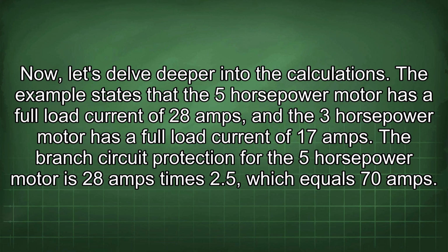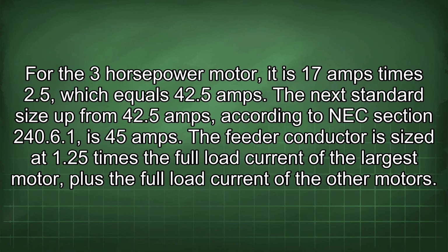The example states that the 5 horsepower motor has a full load current of 28 amps, and the 3 horsepower motor has a full load current of 17 amps. The branch circuit protection for the 5 horsepower motor is 28 amps times 2.5, which equals 70 amps. For the 3 horsepower motor, it is 17 amps times 2.5, which equals 42.5 amps. The next standard size up from 42.5 amps according to NEC section 240.6 is 45 amps.